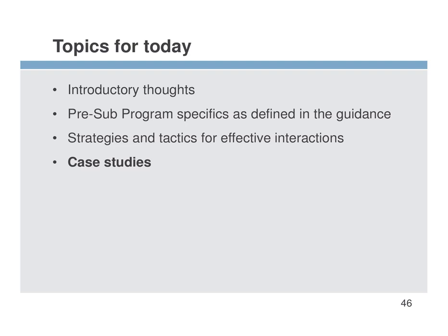Oh, I'm sorry. And it's a submission issue meeting. So FDA has asked for more testing. How much data is necessary to support our perspective that no additional testing is required? So, yeah, it may be that they simply misunderstand your device. So the data you're actually supplying them is more device description. It may be a risk management thing or a different perspective. It may be that you might try to find some clinical literature that might support this as a non-issue, or review the MAUDE database. If the questioner wants to ask something a little more specific, we might have fun turning it into a case study, but I realize you might be sensitive to confidential things.